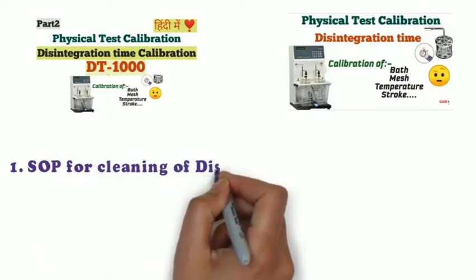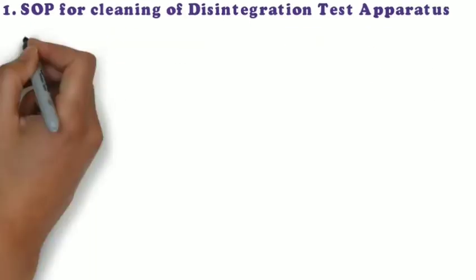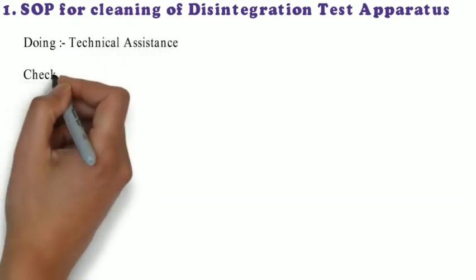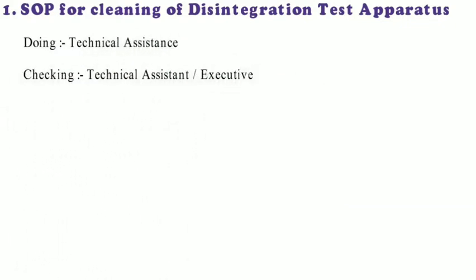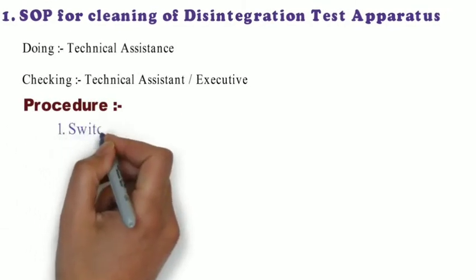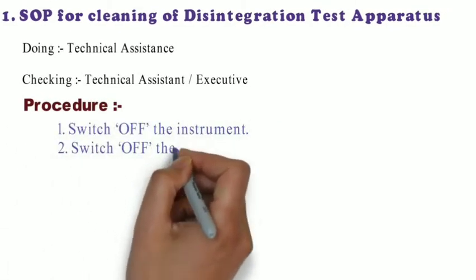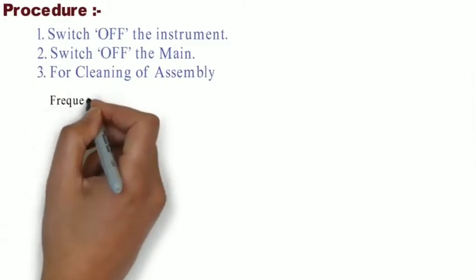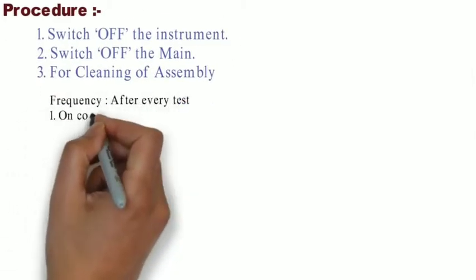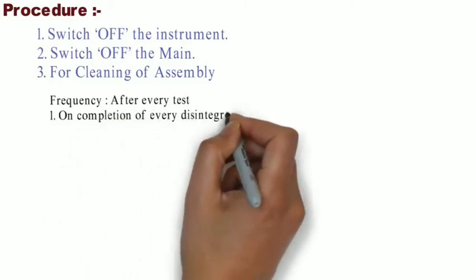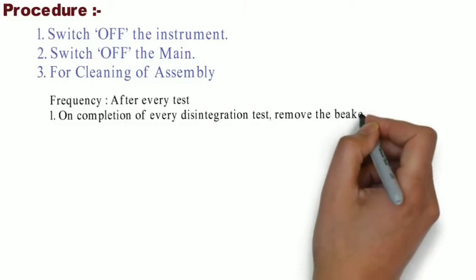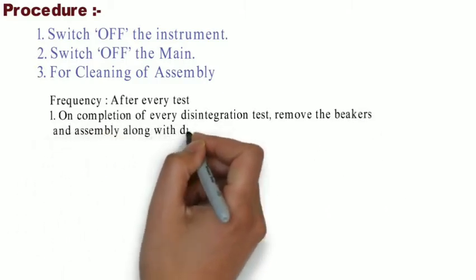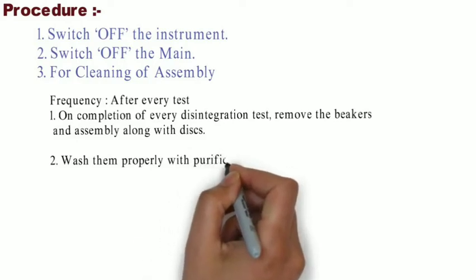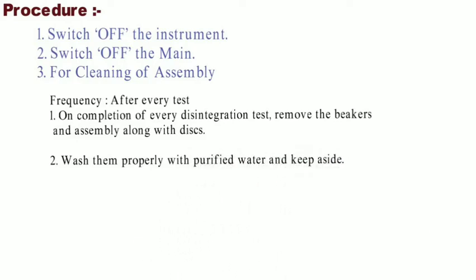We have to start with the SOP for cleaning of the disintegration test apparatus. Here, doing is for technical assistance, and checking is for technical assistance and executive. Its procedure: switch off the instrument, switch off the main for cleaning the assembly. Frequency: after every test you have to do this. First, upon completion of every disintegration test, remove the beakers and assembly along with the disc, wash them properly with purified water and keep aside. What the disc is and what its measurement is, you will get in my disintegration test lecture.